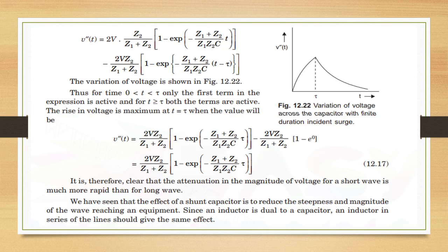The rise in voltage is maximum at t = τ. The second term at t = τ equals zero (e⁰ = 1, making the bracket zero), so only the first term remains. It is clear that the attenuation in magnitude of voltage for a short wave is much more rapid than for a long wave. The effect of a shunt capacitor is to reduce the steepness and magnitude of the wave reaching equipment. Since an inductor is dual to a capacitor, an inductor in series with the line should give the same effect.